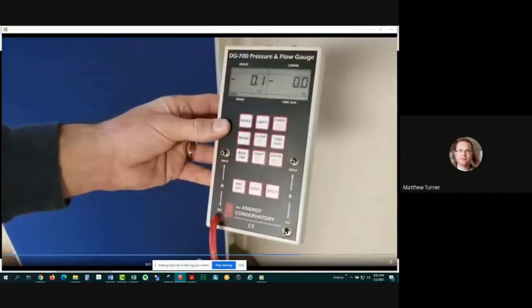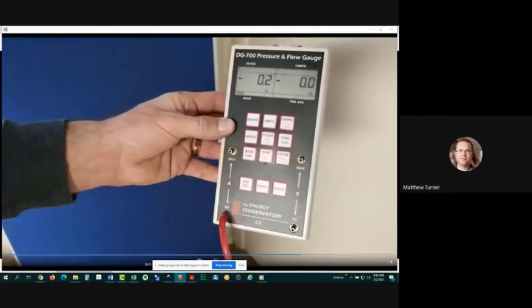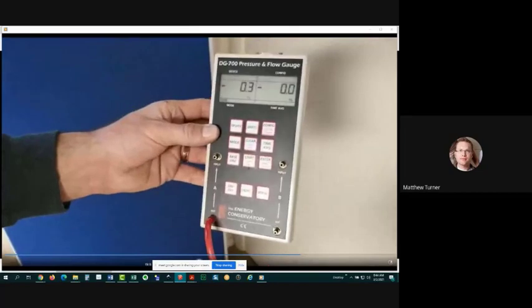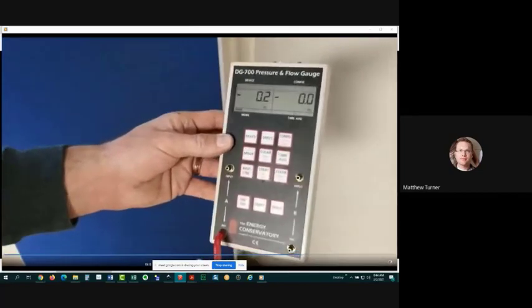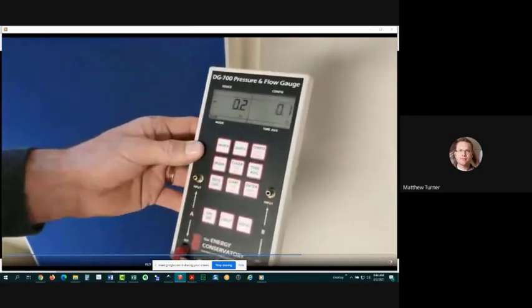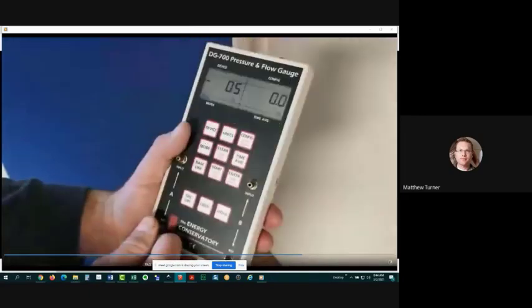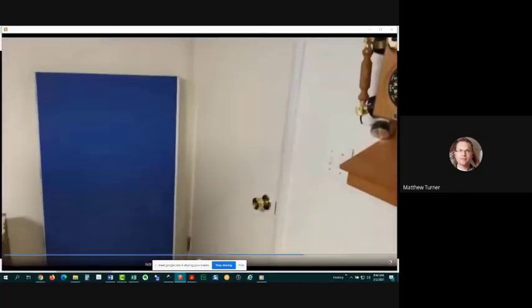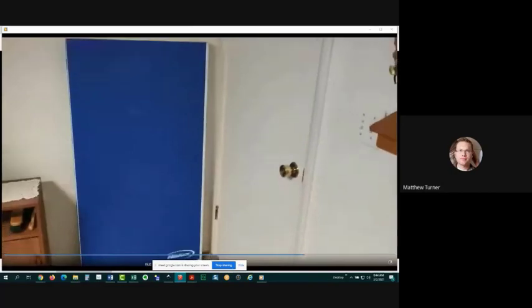So Dalton basically just changed the hoses so that it is as if we're now standing on the other side of the door. Not really. There's not much pressure between the two. Okay, so in this case, we're going to go ahead and indicate that this door is really not having an impact on the CAZ pressure. And so we'll just show that our worst case conditions are what we found a while ago. And I'll go ahead and record those.